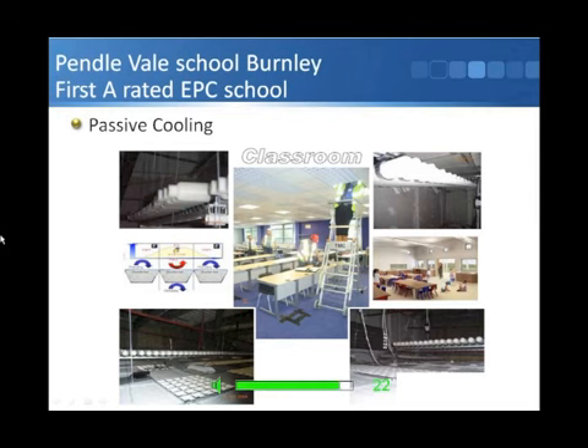And the bottom left-hand corner looking into the ceiling void, you can see the open grid ceiling tiles there which allow the air through. They're not all open grid actually, but about half of them are, and that allows the air through into that space so that the air is cooled and drops back down into the classroom below. And I did this on a 30 pupil classroom and also a 120 pupil seminar room, and it works fine. We managed to avoid air conditioning in both those spaces. We maintain temperature, and it's basically, if you like, free air conditioning.